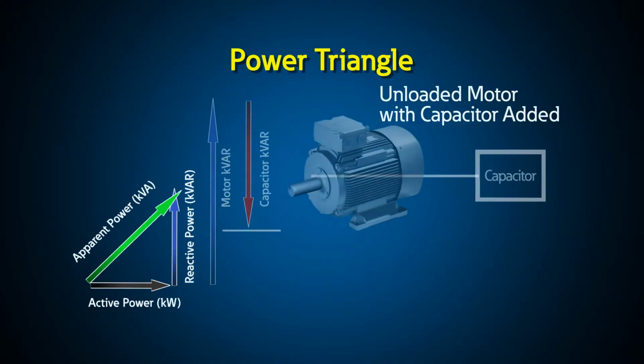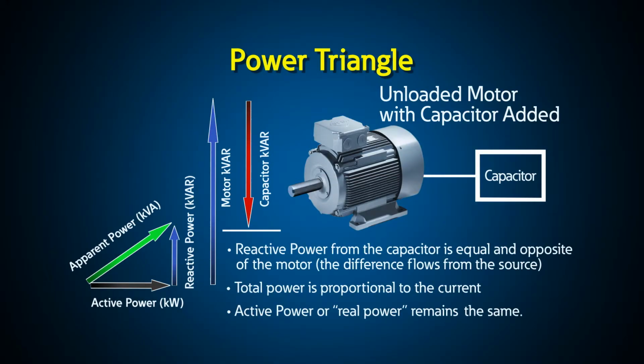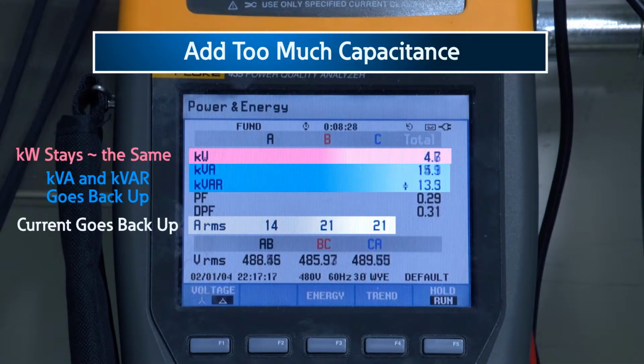Capacitors act to counteract the kVAR required by the motor, and when both the capacitors and the motor are combined, the only power taken from the utility is the real power, if the capacitance is matched precisely with the kVAR required by the motor. Notice that if you add too much capacitance, you could overcompensate and the current would go back up.